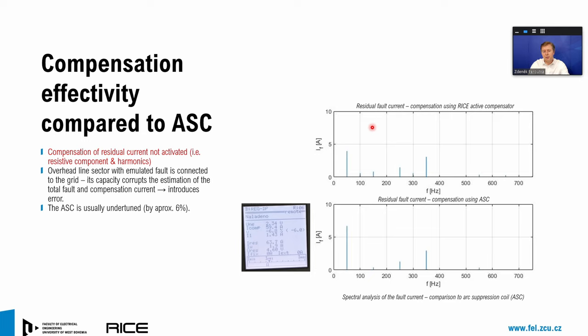And we also stressed our device with a specific emulation of the earth fault, when the earth fault had been emulated on the part of the grid which was switched off. The earth fault was made, and then we turned on this section of the line. And of course, the fault current occurred immediately after switching on this section of the grid.